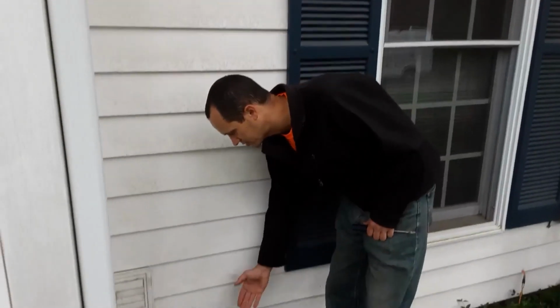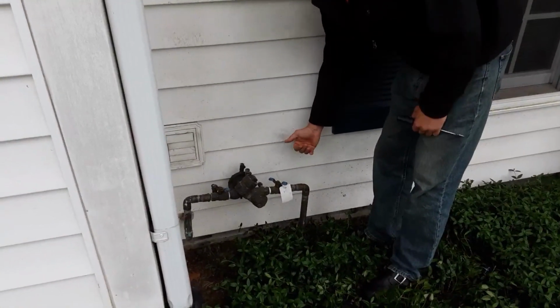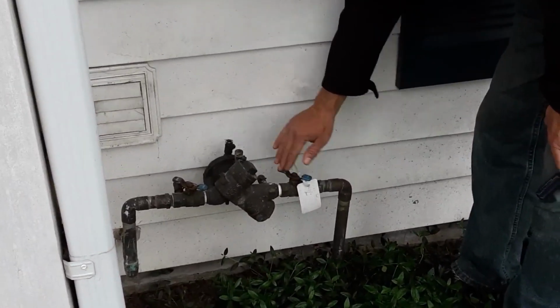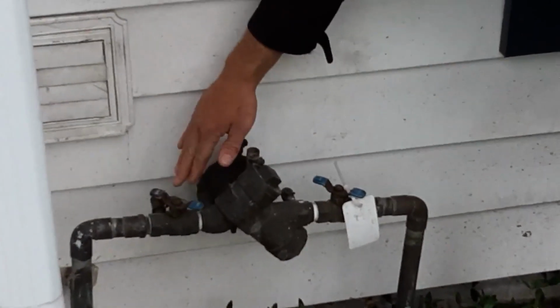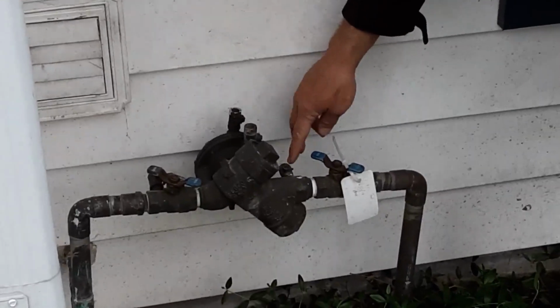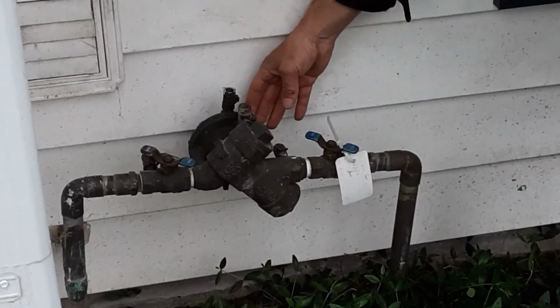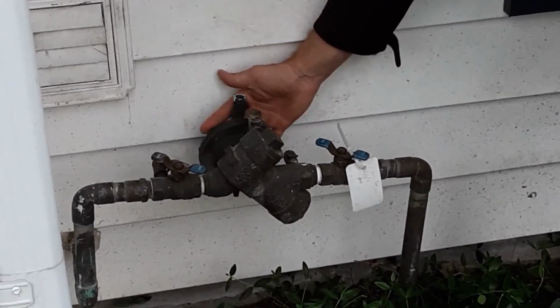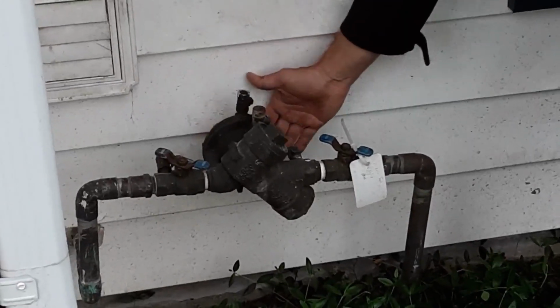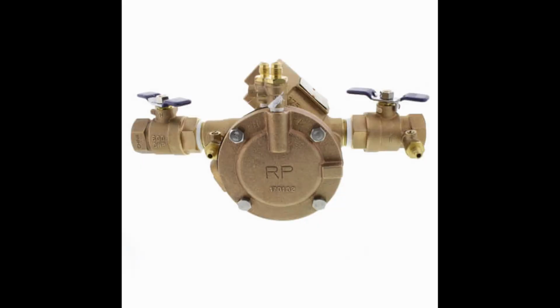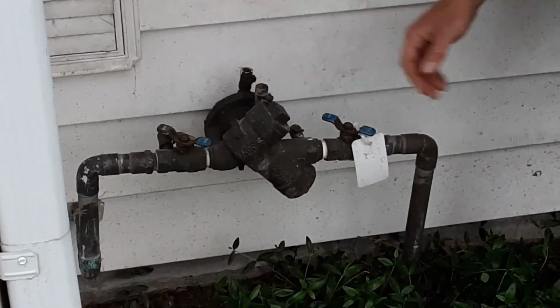Okay, so here we have an irrigation backflow prevention device. This is just one of many different models, but they're all pretty similar. There are 2 water shutoffs, and then there are also 4 test valves, and there's a diaphragm. Most of the time this diaphragm needs to be tightened, so there are 4 bolts on here. They're 1/2-inch bolts. You can tighten those down with a ratchet. And then these 4 test valves need to be closed.